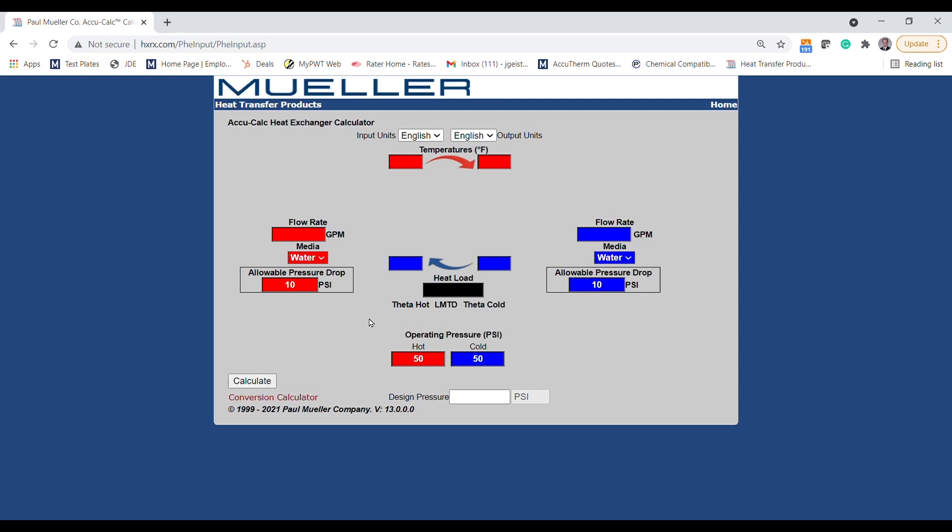The sizing tool will only function if five out of the six available fields have been completed, with the final field allowed to float. By entering the service fluid properties last, this will ensure that you are not floating a critical value of your load fluid.